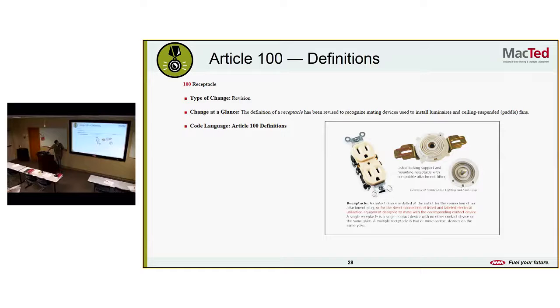These are kind of new. These are a new type of luminaire receptacle for attaching lights to. They've revised the definition of receptacle. So now the definition is recognizing mating devices used to install luminaires and ceiling suspended paddle fans. Used to just be like, basically that was a receptacle, but now they have these mating devices for fans and lights. They just kind of stick together. They can rotate a little bit. Makes it easier to plug things in, replace parts.